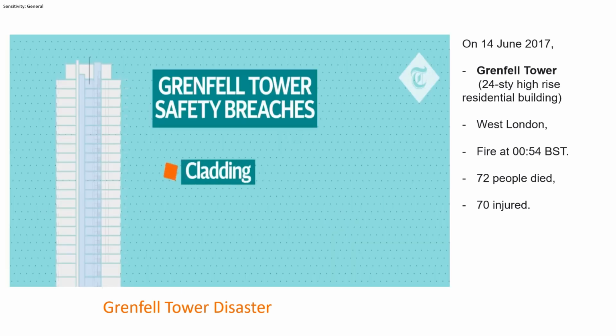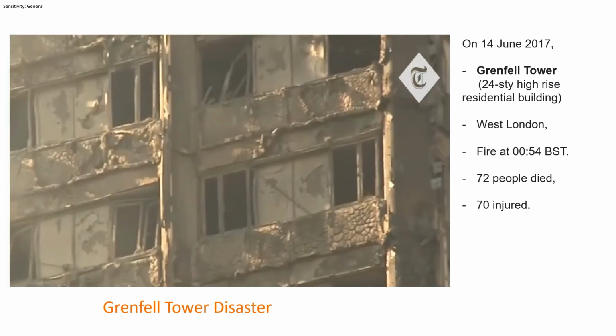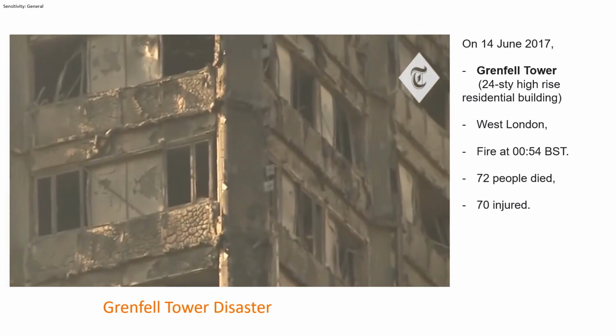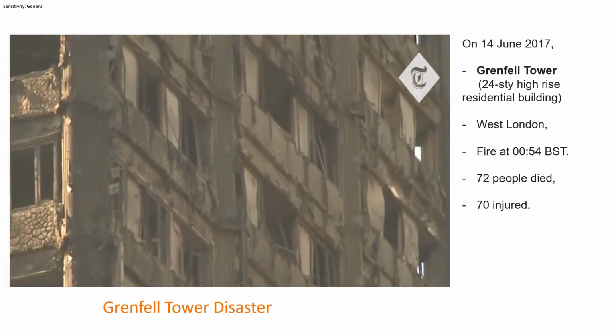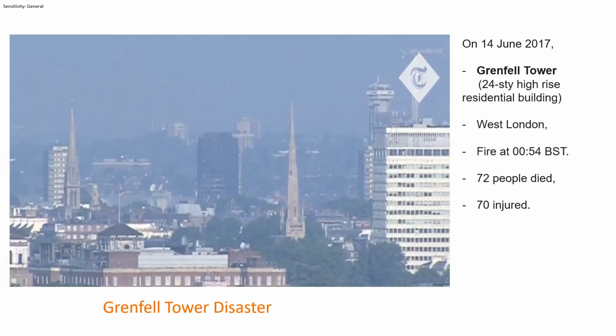Other safety breaches were cited for the devastating spread of the flames. The windows lacked fire-resisting cavity barriers and were surrounded by combustible material. That meant there was a high probability of fire spreading to the cladding.